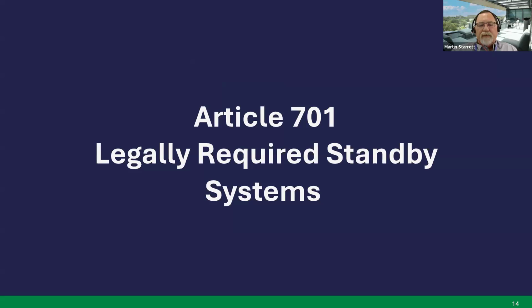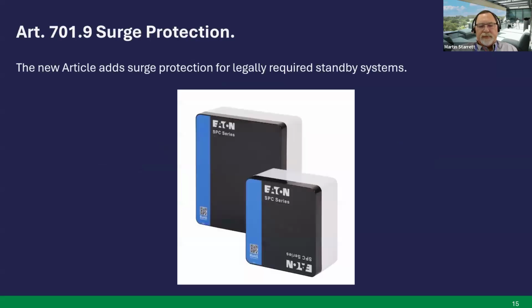Article 701, legally required standby systems. So Article 701.9, surge protection. This new article adds surge protection for legally required standby systems. Next slide.